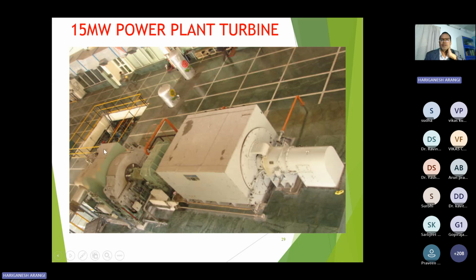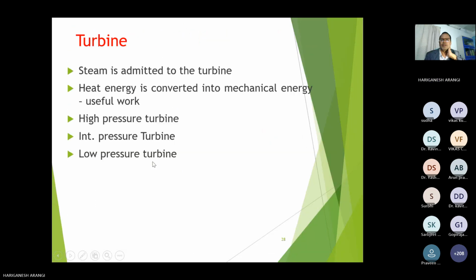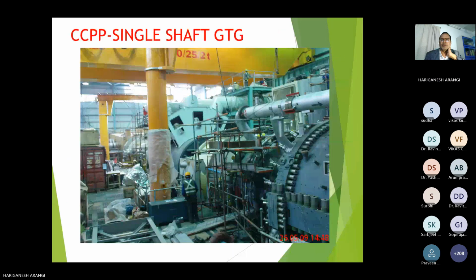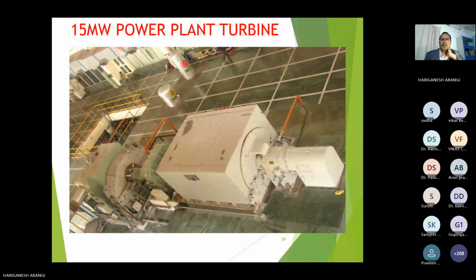Here in this first green color, the steam enters the turbine and rotates. This is the low temperature the steam gets after expansion. The turbine speed will be around 6,000 to 7,000 RPM for low capacity, whereas for high capacity it will be 3,000 RPM. And the middle one shown, the middle green color, is the gearbox.